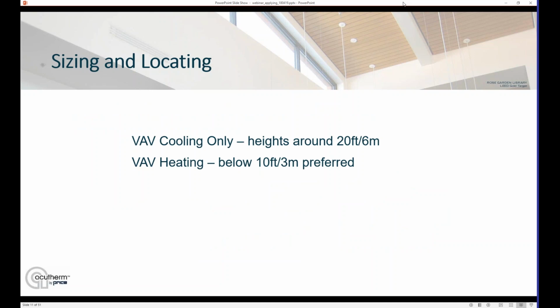The diffusers work very well in cooling up to ceiling heights of around 20 feet. But in heating, it's a little bit more challenging to get that warm air to blow down. We recommend 10 feet height preferred. You can get away as high as 12 feet, but really 10 feet preferred to make sure you get good room air mixing even in the heating mode.